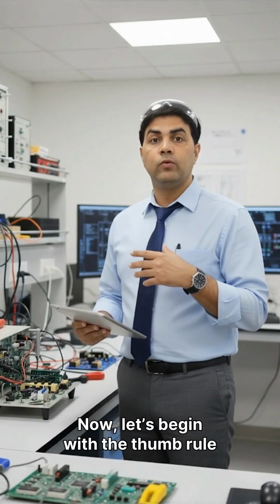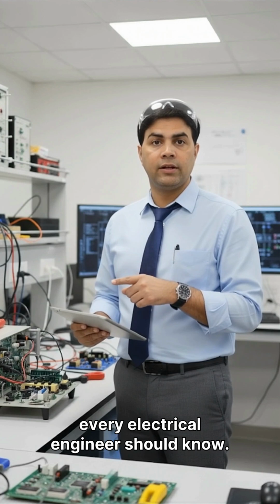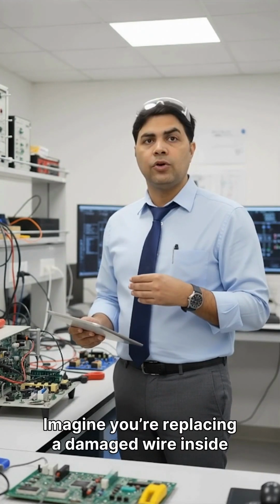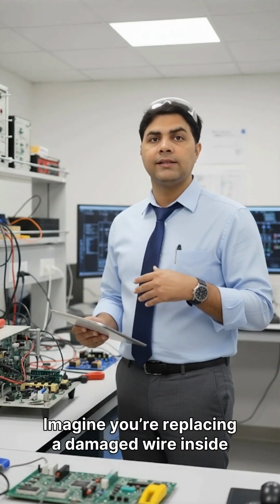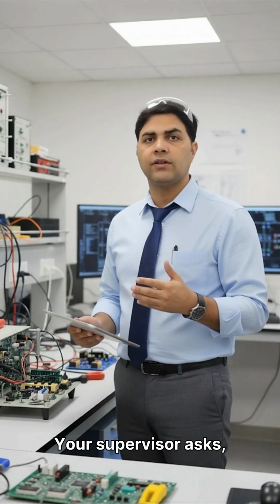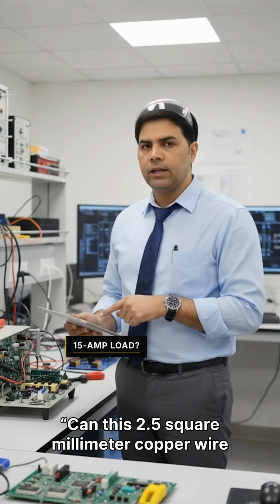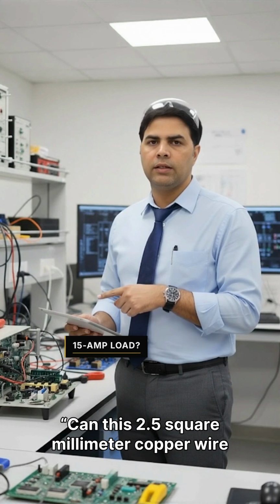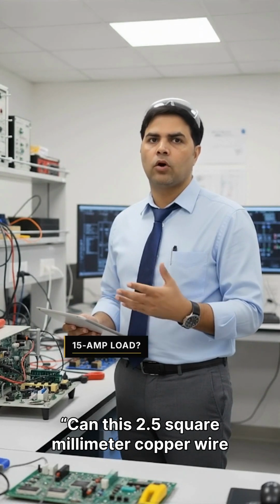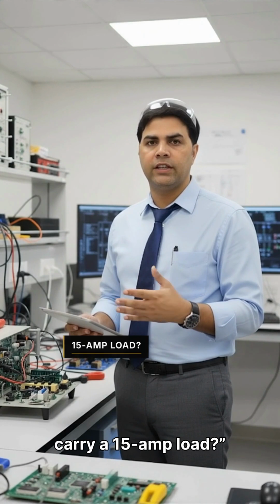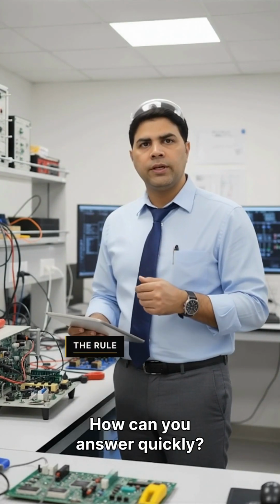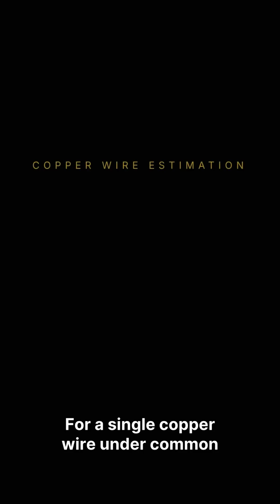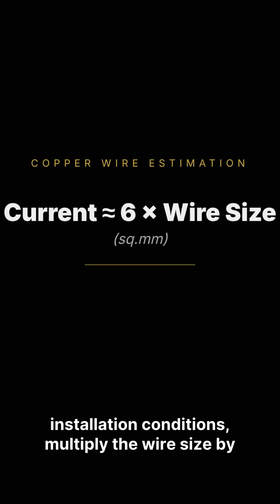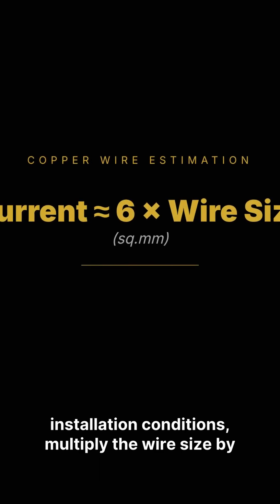Now let's begin with the thumb rule every electrical engineer should know. Imagine you're replacing a damaged wire inside a control panel. Your supervisor asks, can this 2.5 square millimeter copper wire carry a 15 amp load? How can you answer quickly? Here's the thumb rule. For a single copper wire under common installation conditions, multiply the wire size by 6.